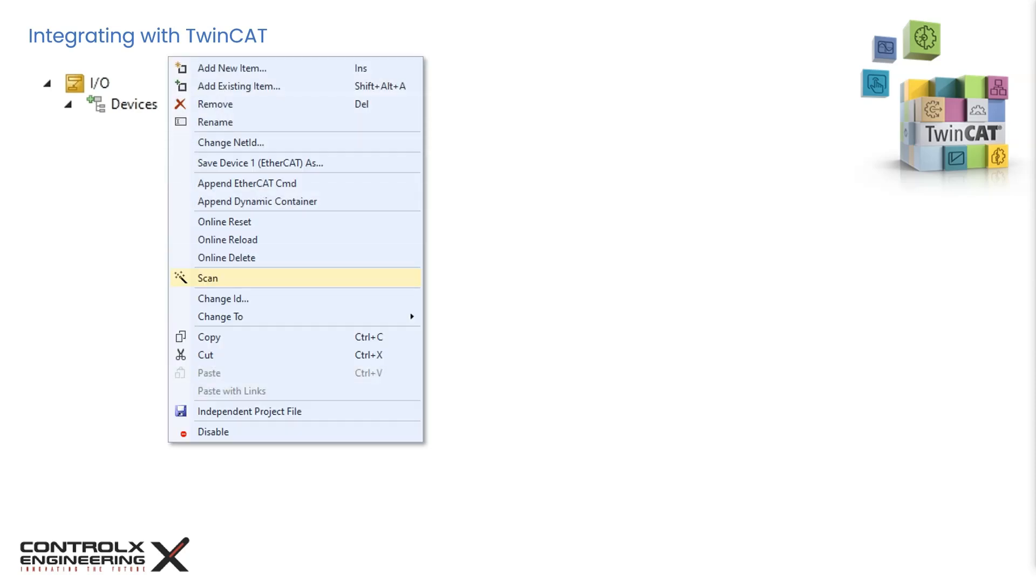If the EtherCAT configuration is created online through scanning of a physically connected EtherCAT device and no corresponding ESI description file is available for the slave device, the system manager will ask via a dialog box whether the description stored in the device's EEPROM should be used. The system manager needs this information for setting up the cyclic and acyclic communication with the slave device correctly.